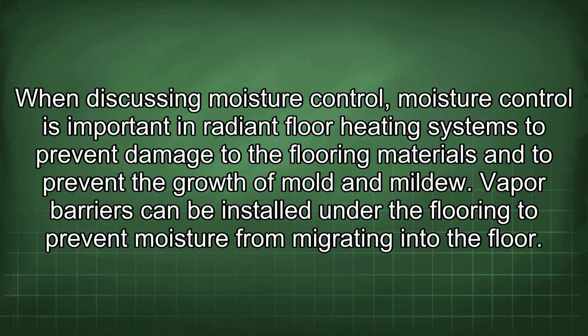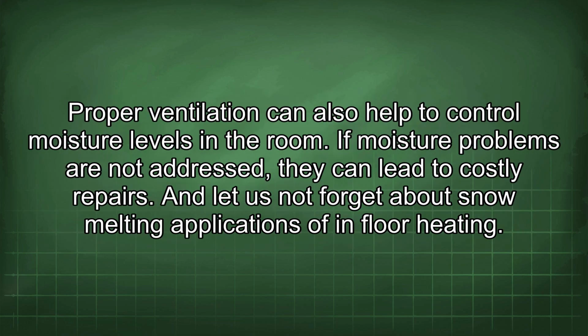When discussing moisture control, it is important in radiant floor heating systems to prevent damage to the flooring materials and to prevent the growth of mold and mildew. Vapor barriers can be installed under the flooring to prevent moisture from migrating into the floor. Proper ventilation can also help to control moisture levels in the room. If moisture problems are not addressed, they can lead to costly repairs.